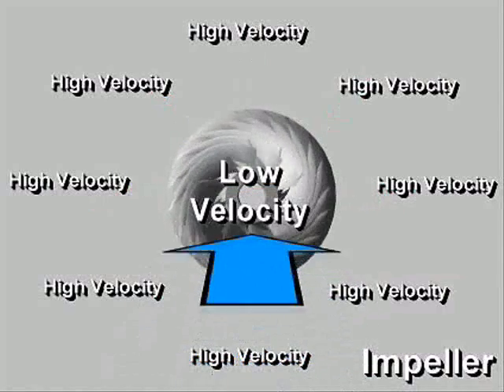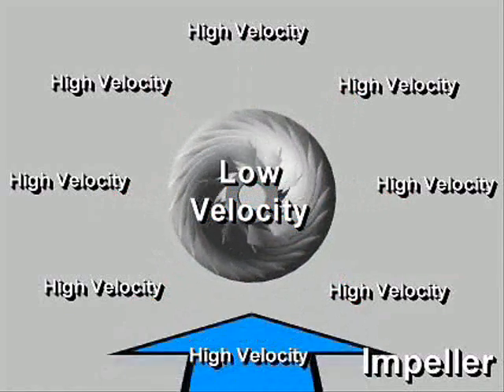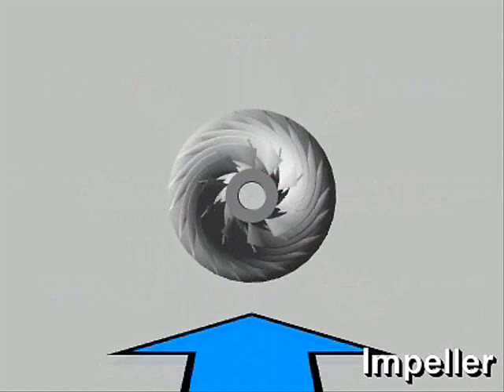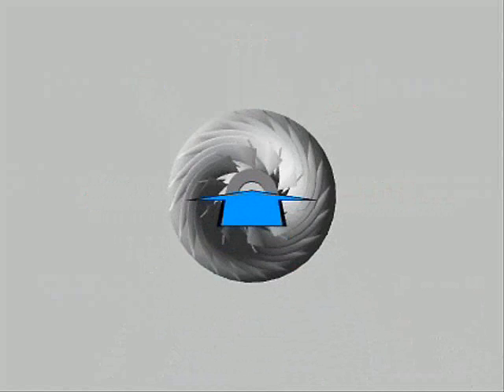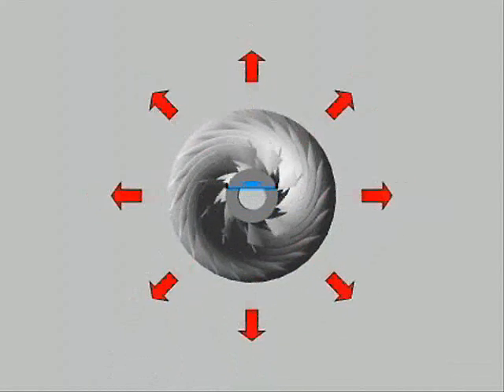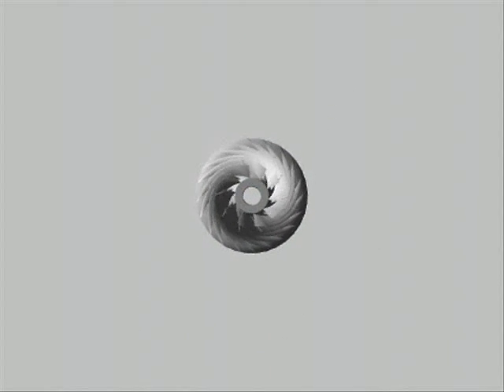This means that the impeller transfers its rotational energy to the vapor, but high velocity does not relate to high static pressure. To achieve the desired pressure increase, or compression, the vapor must be slowed down, converting its velocity pressure to static pressure.